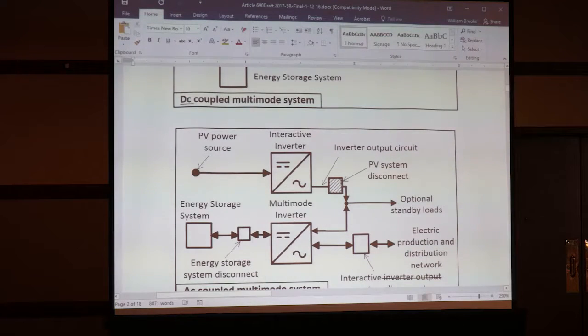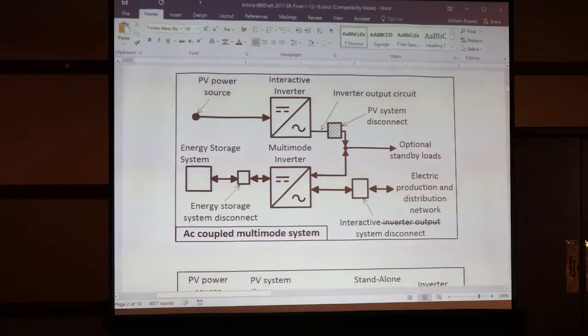Now, we could have multiple interactive inverters, could we not, in an AC coupled system? So each one of those would be a PV system disconnecting means. All right? And the code allows us to have up to 6 PV system disconnecting means in one system, and they would have to be grouped and connected together, or grouped together, is the way they said.